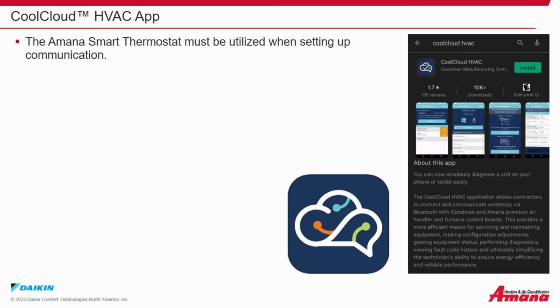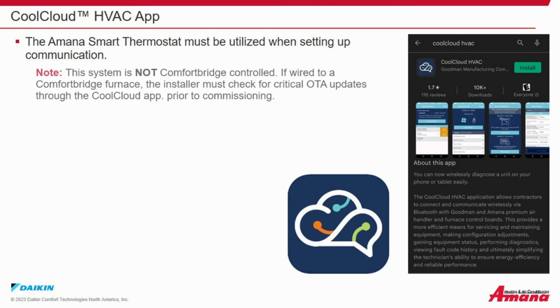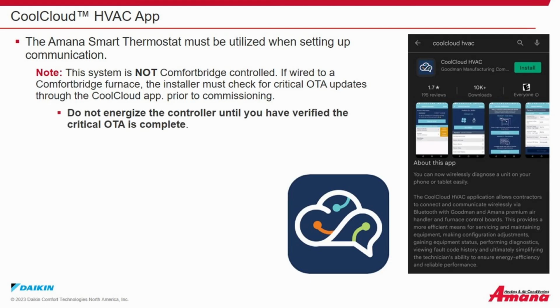The Cool Cloud HVAC app. The Amana Smart Thermostat must be used when setting up communication. Note, this system is not Comfort Bridge controlled. If wired to a Comfort Bridge furnace, the installer must check for critical OTA updates through the Cool Cloud app prior to commissioning. Do not energize the controller until you have verified critical OTA is complete.